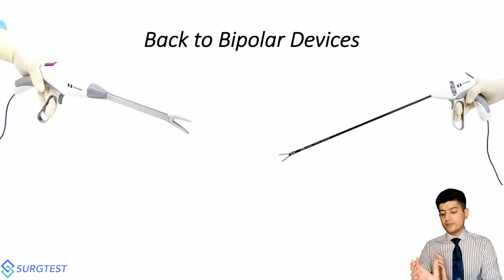So I'm going to again come back to dedicated bipolar devices and vessel sealers. Now, an important thing that happens with these vessel sealers is that when you press the activating button, there are a bunch of different beeps that come out. It beeps constantly and then eventually has a very strong change in beep and then it stops. What exactly is happening over there? Well, when you're firing, you've got tissues within these devices. These are two dedicated vessel sealers that you're seeing on screen. One is open and the other is laparoscopic.